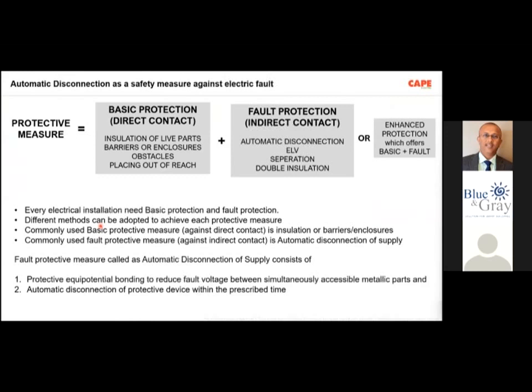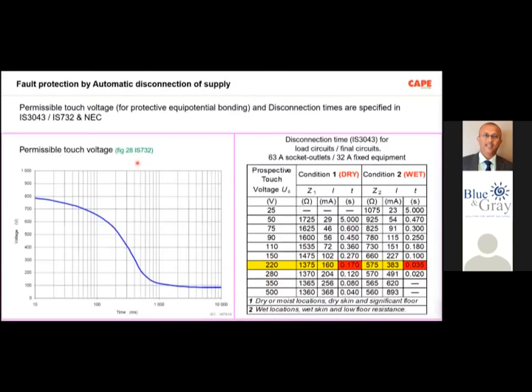Basically, shock protection is achieved by 2 methods: basic protection and fault protection. We have explained it in our earlier webinars, but still I will explain it again. Basic protection means protection against direct contact, and fault protection means protection against indirect contact. So different techniques are used for this particular purpose. The most commonly used fault protective measure is called automatic disconnection of supply. So in the standards and technical books, you will be able to read it as automatic disconnection of supply.